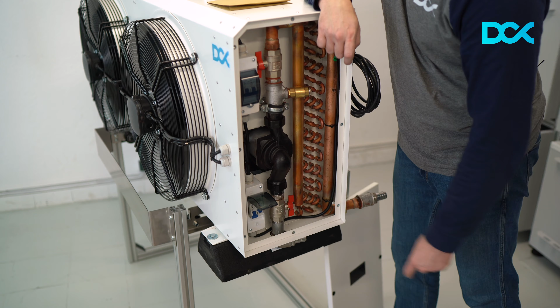Now there are also two switchgear boxes, one at the bottom, one at the top. The first one from the right is starting up the whole system. So it's basically protecting all the components here. The second one powers up the pump. It should be started only when the system is fully filled with the water or water glycol mixture. So then we're starting the pump.